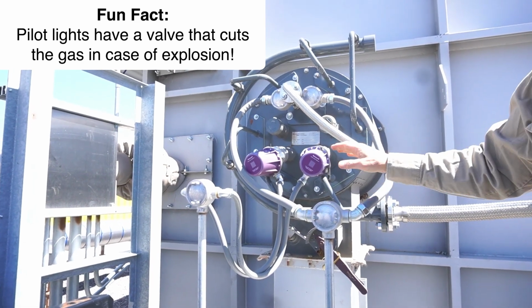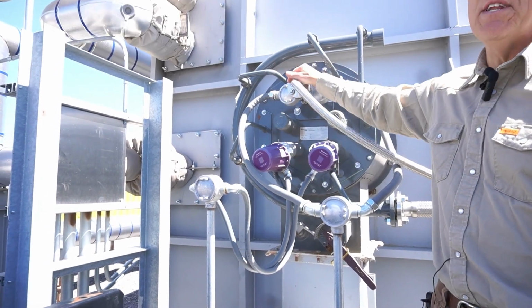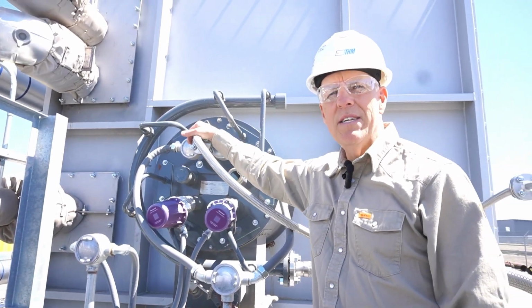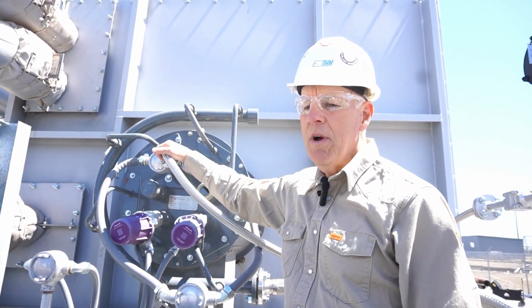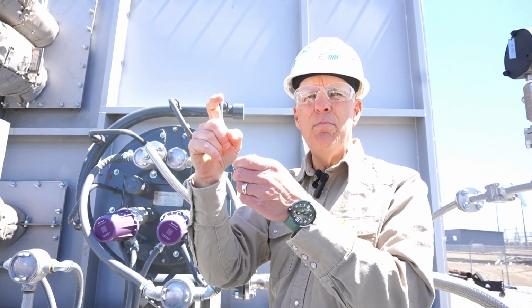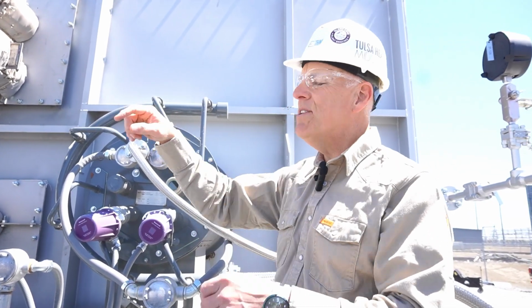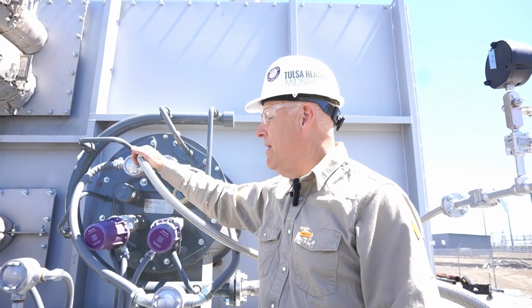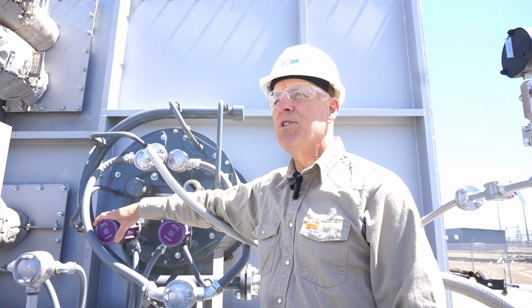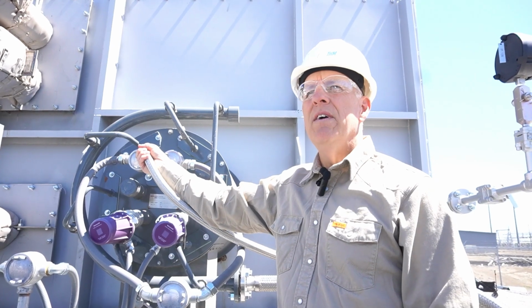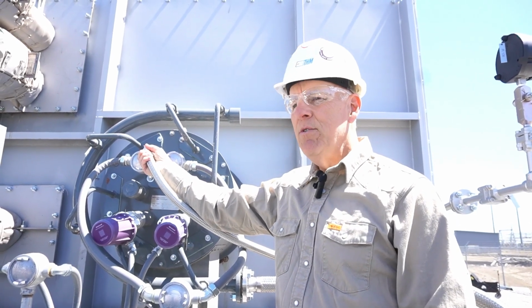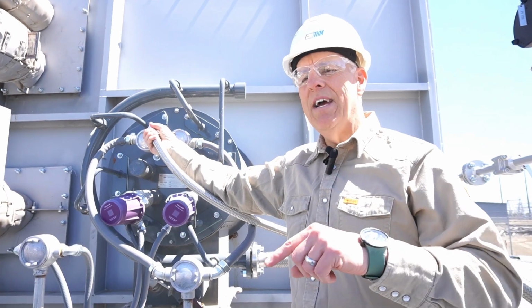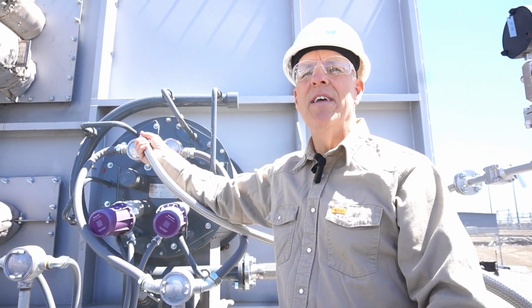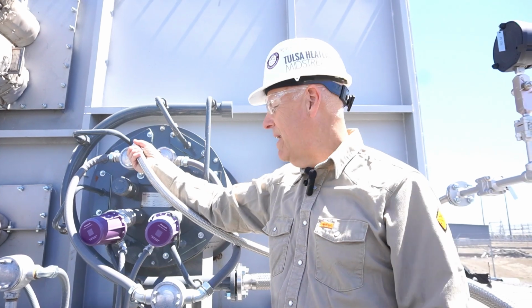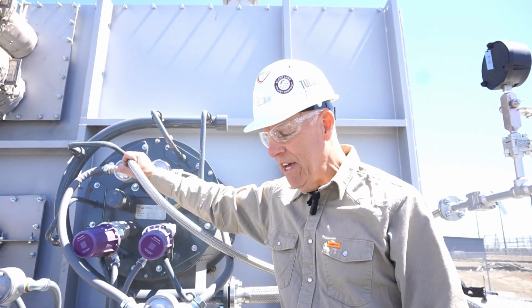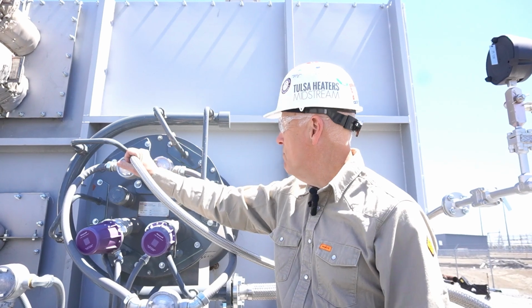This customer likes a standing pilot, or pilot that's on all the time. So besides the UV scanners, this particular pilot has what's called a flame ionization rod. The flame ionization rod is essentially a rod that sticks into the pilot flame and tells you, yes, I've got flame, or no, I don't. They also have that backup with the scanner. So it's important really to know, do I have flame? If I do, I'm happy. If I don't, but I think I have gas, but I don't have flame, but I have gas on, it's not happy and everything gets shut down. So sensing the flame, seeing the flame is really, really important.